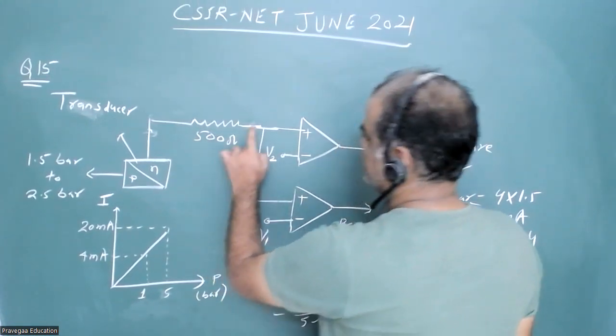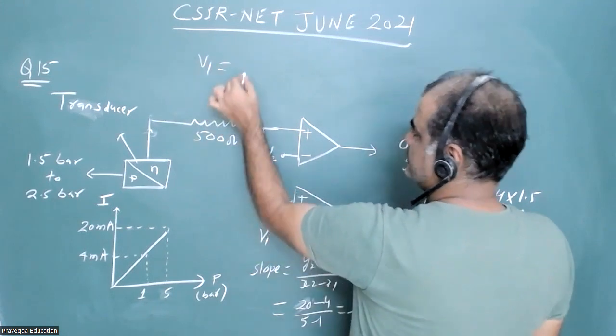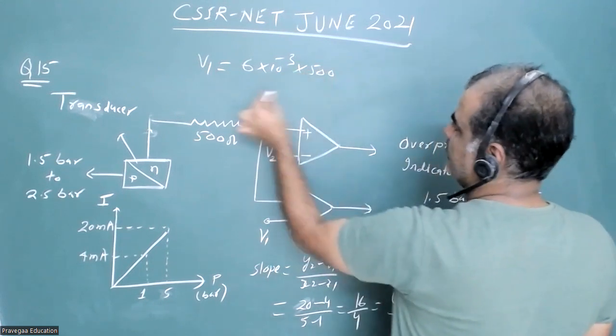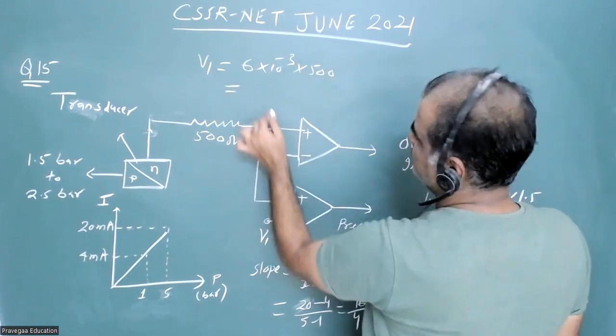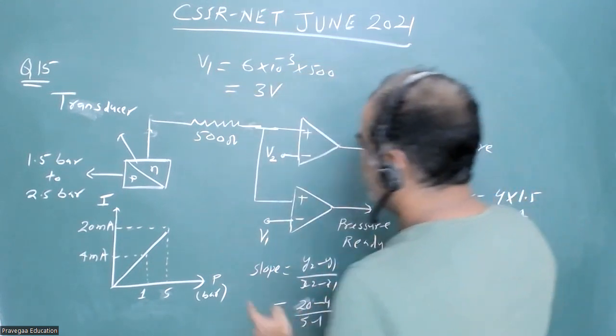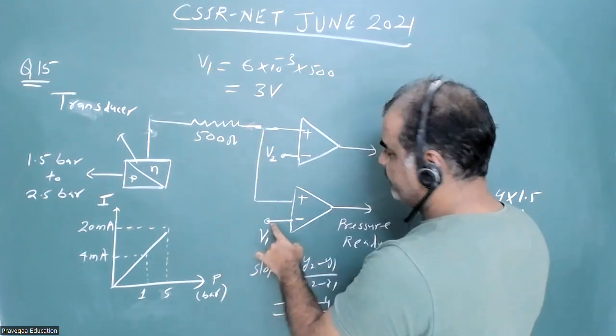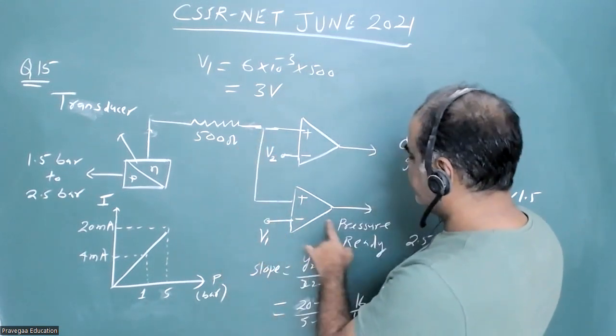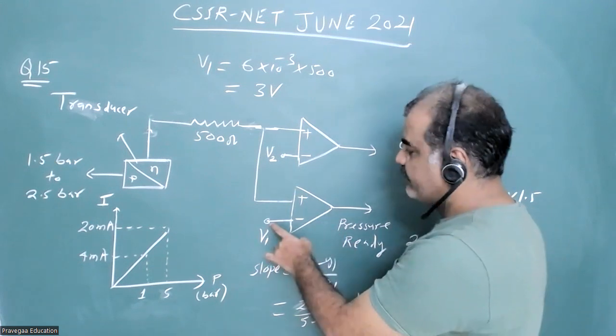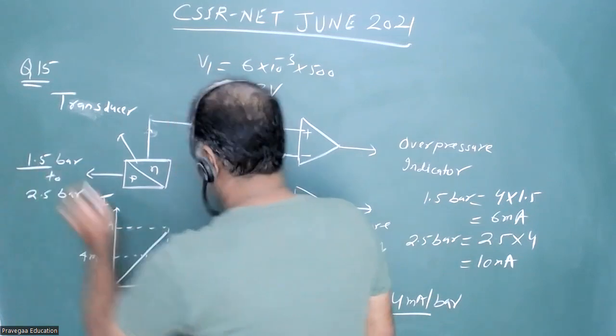When we are getting 6 milliampere current, the voltage at this point will be 6 milliampere × 500 ohms, which gives 3 volts. So when the voltage here reaches 3 volts, it shows that the pressure is at 1.5 bar and our experiment is ready.